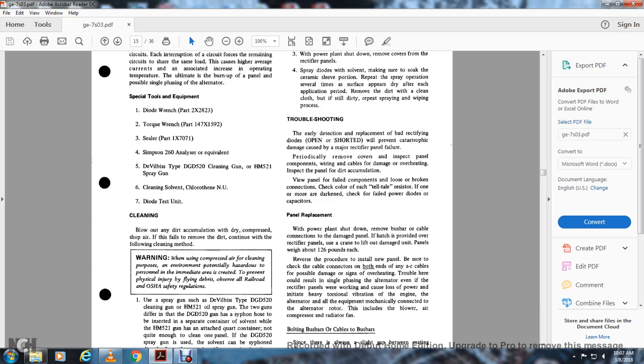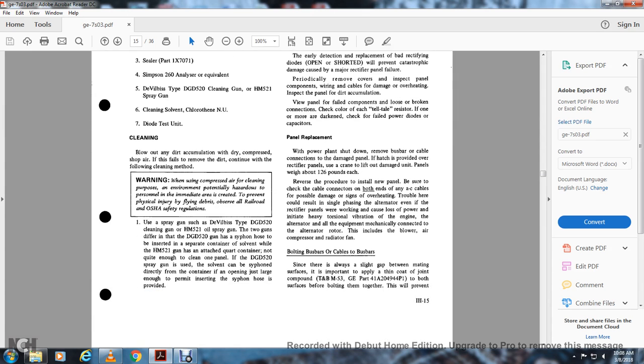Troubleshooting: early detection and replacement of bad rectifying diodes, open or short, will prevent the catastrophic damage caused by a major rectifier panel failure. Periodically remove the cover to inspect the panel, components, and wiring cables for damage and overheating. Inspect the panel for dirt accumulation, failed components, and loose or broken connections. Check the color of each of the telltale resistors. If one or more are darkened, check for failed power diodes and capacitors.